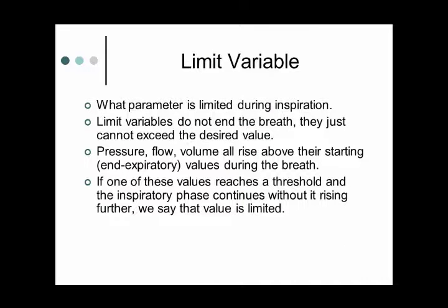Now let's talk about limiting. Some parameter is limited during the course of the breath. The limit variable remains constant through that phase, but doesn't end the breath. So it rises to a particular thing that you dial in and stays there until the breath ends. But it doesn't end the breath.